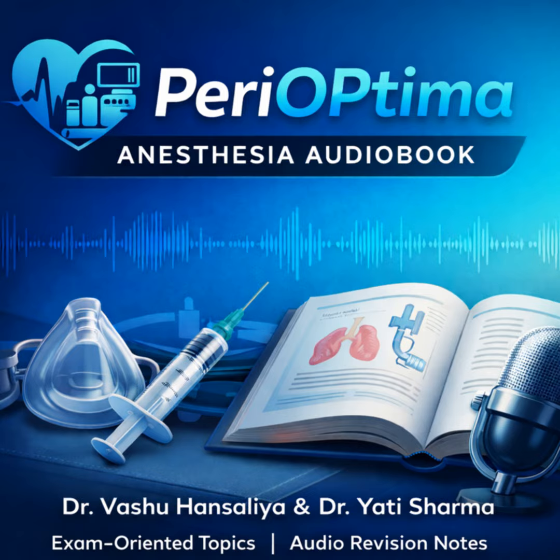Safety check for Bain is Pethick's test. For Circle, it's valve competency and the absorbent status. Right. Resistance is low to moderate in the Bain, but high in the Circle. Suitability for long cases. Less so for the Bain due to poor heat and humidity, but excellent for the Circle. And finally, cost. The Bain is cheaper to buy, but expensive to run because of the high gas flows. The Circle is expensive to purchase, but cheap to run.